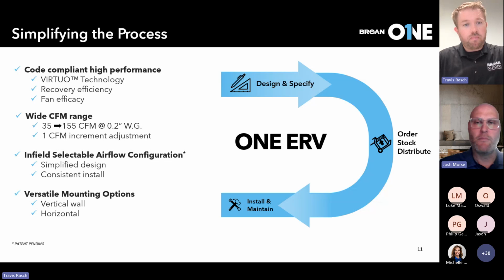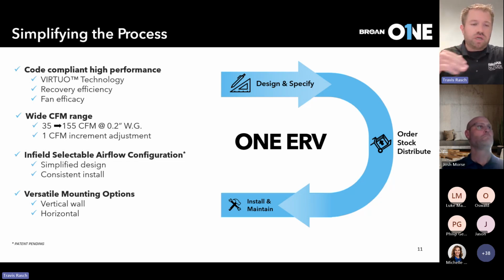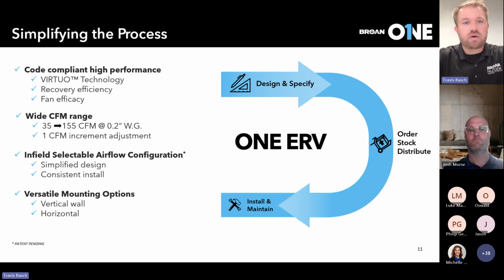We got one more question from Kurt. We're showing 0.2 water gauge static pressure, and he understands that may not be a great real world application, and he's wondering what we're at for 0.4, 0.6 and further. I'll go off the top of my head. At 0.4, we're at 146 CFM. At 0.6, I believe we're at 138, maybe 136, somewhere in that range. Understand that our fan curve stays pretty flat as static pressure increases. It really comes back to the ECM motors and their ability to overcome that static pressure, as well as the design of the recovery core, making sure we're still getting the sensible efficiency we want while still moving air through. The spec sheets are out there, but going from memory, at 0.4 we're at 146 CFM, and at 0.6, 138. So staying pretty flat, which is good from an application standpoint and for design purposes.